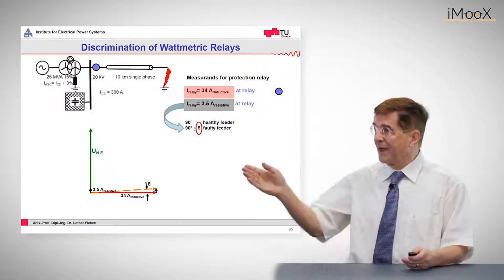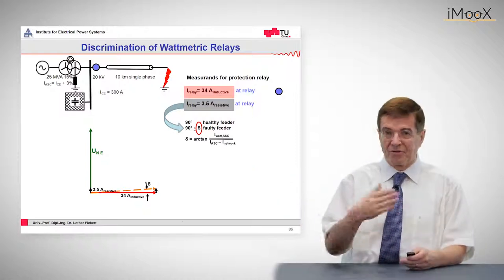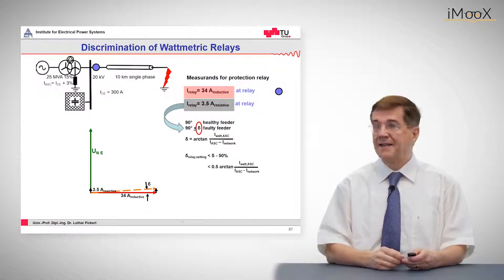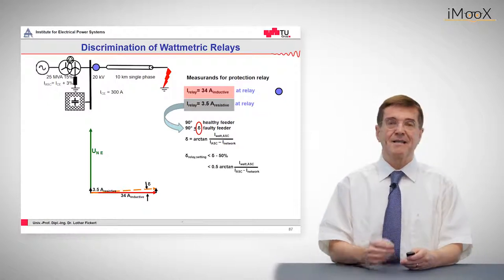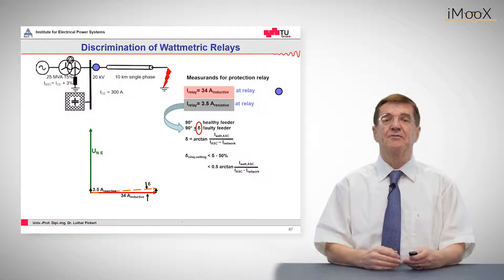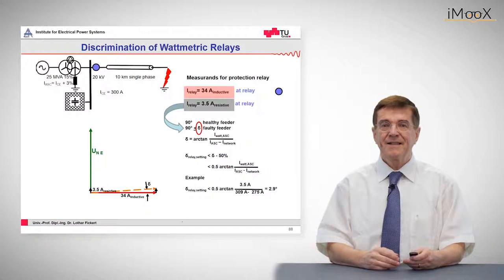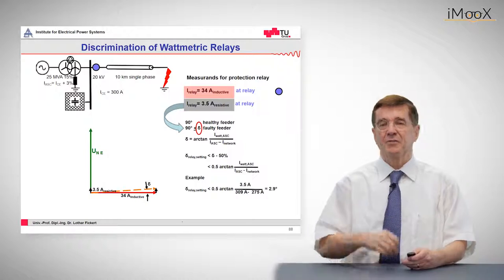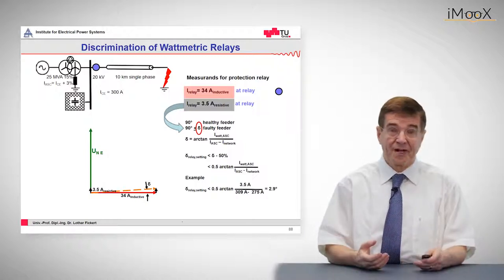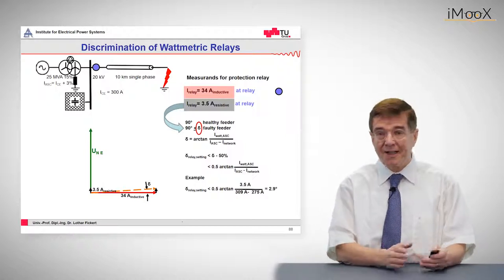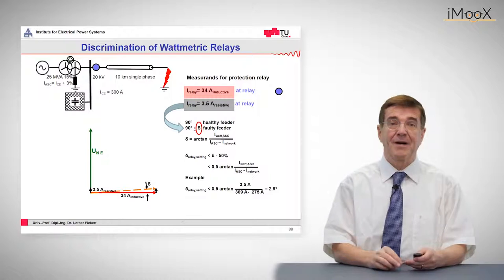Now let's see, this small angle, what is it made of? It's the arc tangent of the resistive current divided by the residual reactive currents, and then we demand that the relay setting should be 50% below it, so that we have enough discrimination margin for safe and secure picking up of the relay. And in this case, we see here that these values are very, very small. If you take it in terms of time, the angle of 2.9 degrees electrical correspond to a time lag or time shift of 180 microseconds.